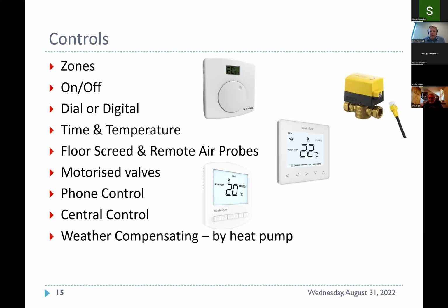You can have battery operated Wi-Fi thermostats. You know yourselves, at the moment there are so many types of solutions out there. They can all be integrated with these systems. You just need an enable to a motorized valve, as we have here, and the motorized valve will in turn give an enable signal to a heat pump or boiler, and then off you go. We can do heating and or hot water.